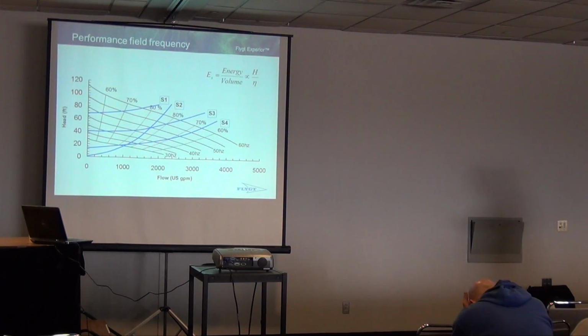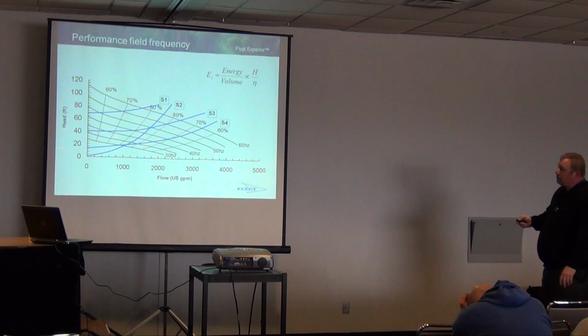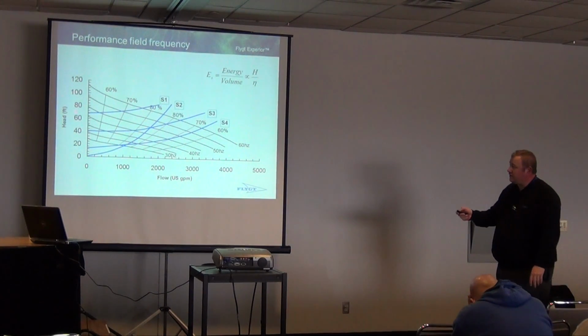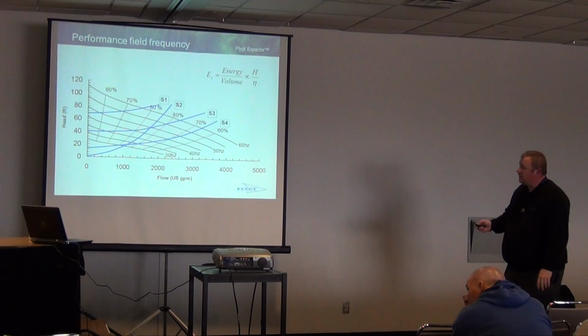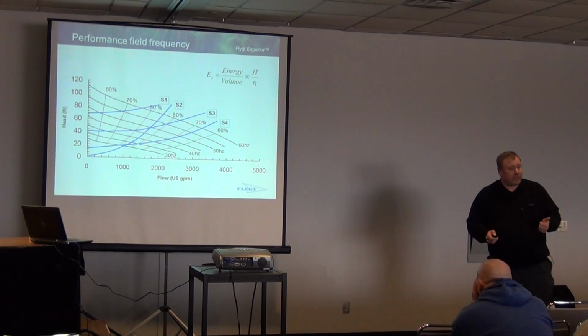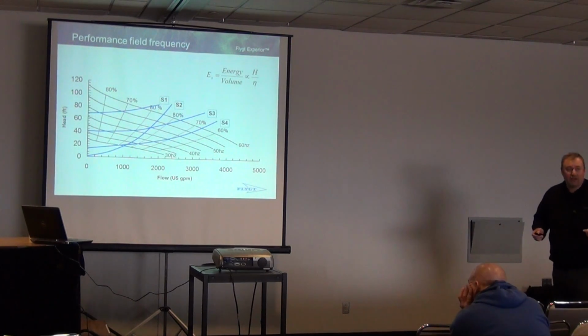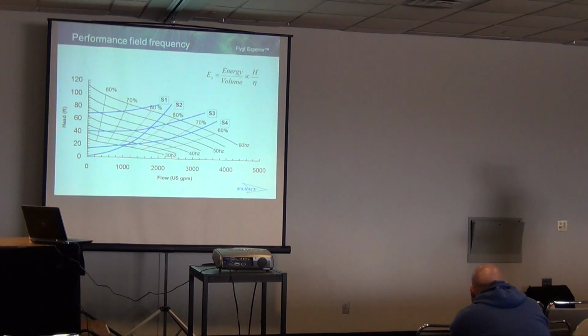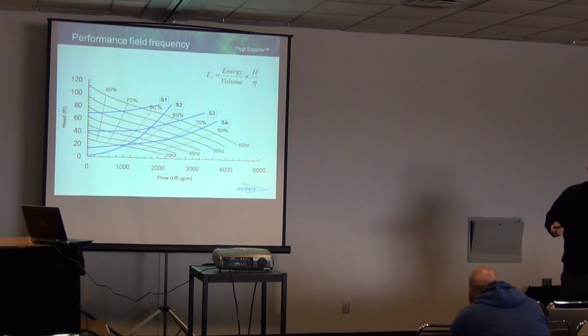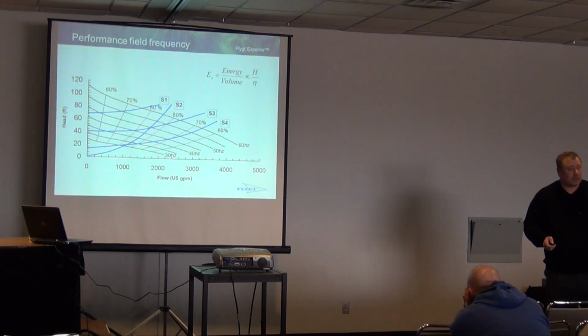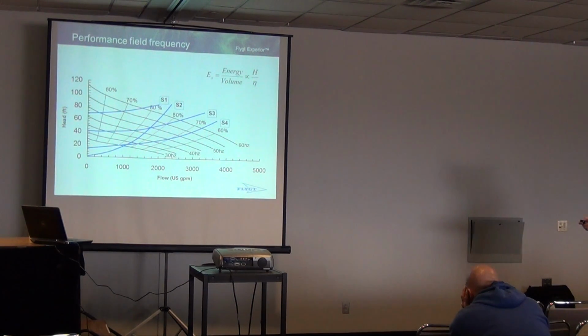One of the things I want to talk about is that we all know we have a total dynamic head condition on a pump station. Depending on how big your force main is, how much flow you have, how much static head and C-factor loss you have in your pipe, your bends, and your check valves, all those things determine how the system curve will lay across that pump curve. And I just want to point out a couple things quickly.